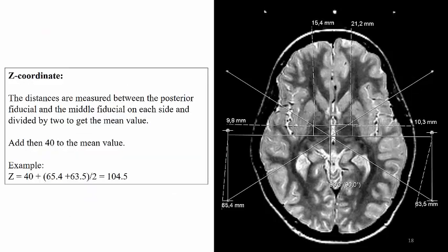In order to get the z-coordinate, we measure the distance between the posterior fiducials and the middle fiducial on each side and divide by 2 to get the mean value. We then add 40 to the mean value.